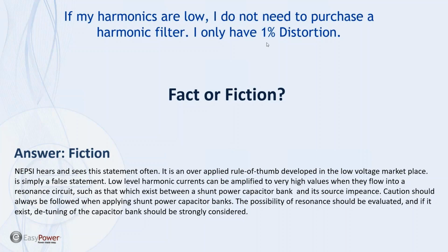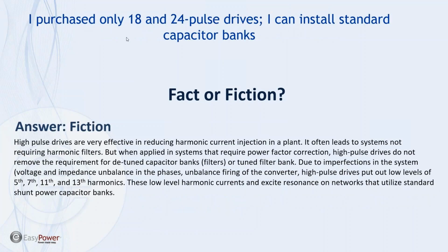If you have low distortion, you don't need to install harmonic filters, but if you have plans to install power factor correction, even with a few % distortion, you need to consider resonance in the system and determine if resonance is going to be an issue. This is an extension of the statement I just made.